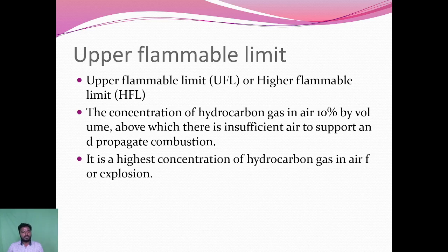Upper flammability limit: the upper or higher flammability limit is the concentration of hydrocarbon gas in air, about 10% by volume, above which there is insufficient air to support and propagate combustion. It is the highest concentration of hydrocarbon gas in air for fire or explosion. Beyond this limit there is no fire. In between the lower and upper flammability limits is the flammable area.